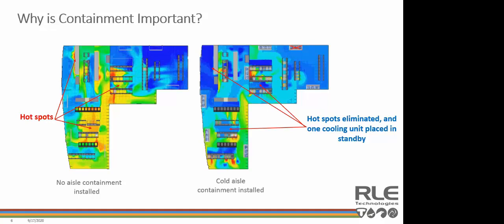You can see that there are cold aisles with relatively warm supply of air and several hot spots. This is mostly due to differences in server racks. Some may need more cooling, some may have a higher IT load than others. Mixing of hot air and cold air within the space only makes this worse by recirculating already warm air through the server rack, which makes the hot spot even worse. So in the no aisle containment model, all 6 cooling units are on and supplying cold air to the underfloor plenum.